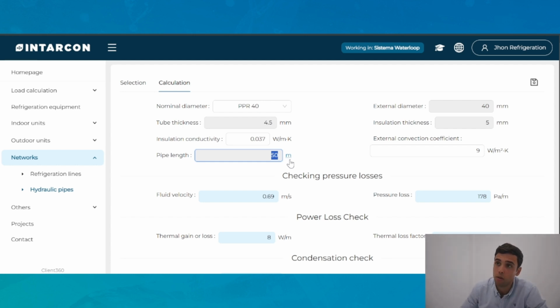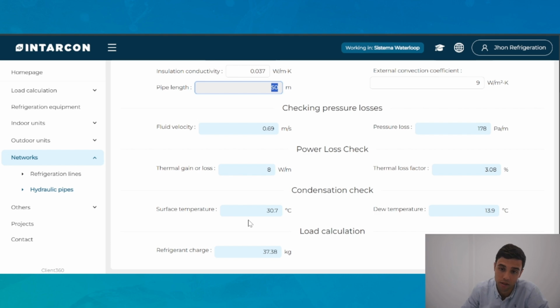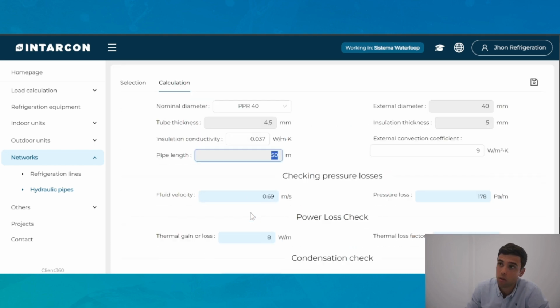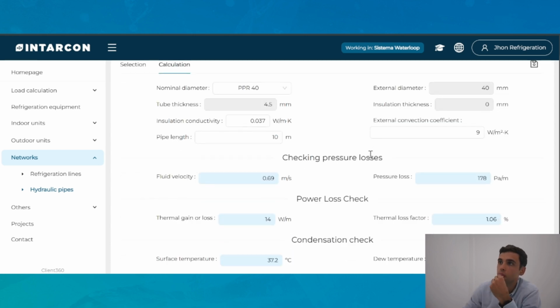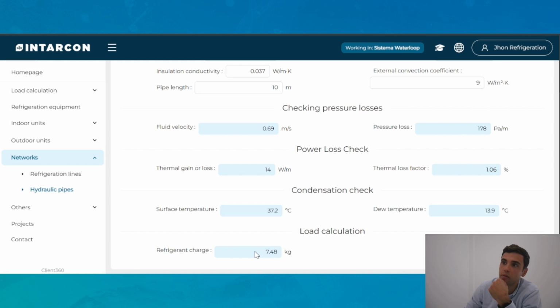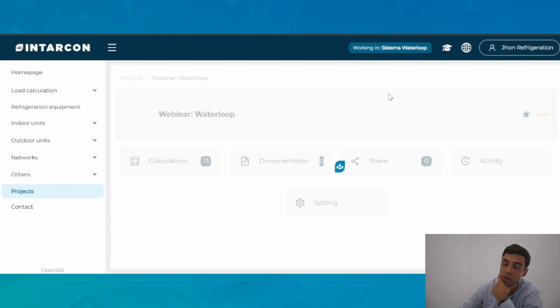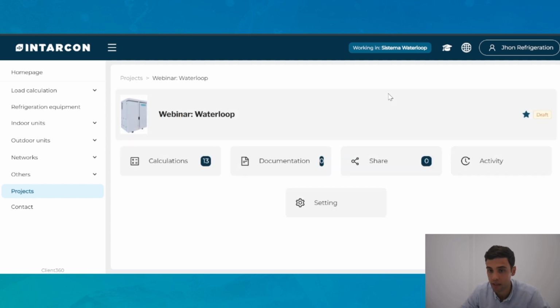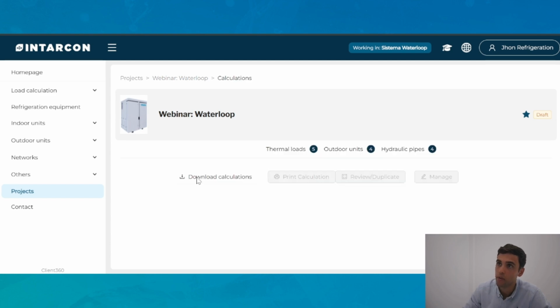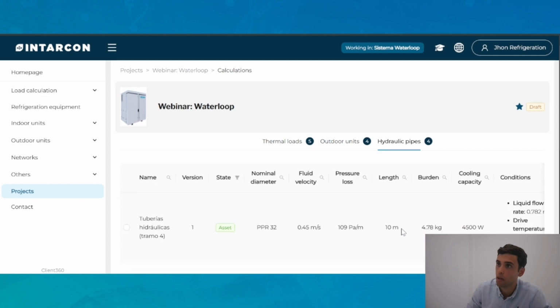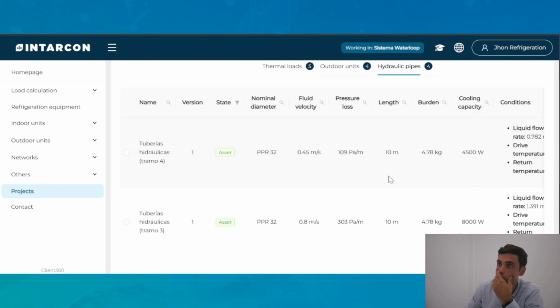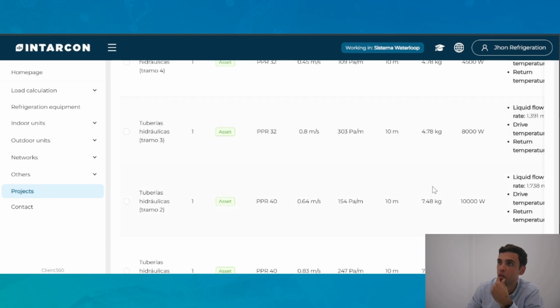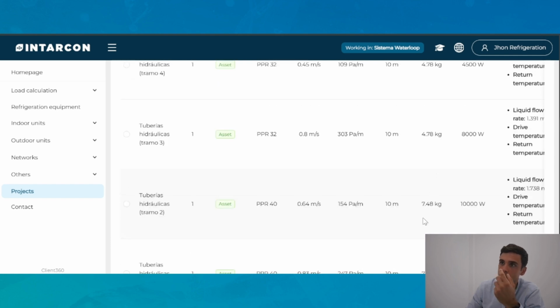Also important, the total amount of refrigerant charge that we will have, in this case it will be water. It depends on the nominal diameter and the pipe length, in this case, for example, 10 meters. It calculates also the total refrigerant that you will have, in this case water. So finally, you will have a holistic layout of the installation where you can see very precisely the total amount of refrigerant charge that we will have in each part.